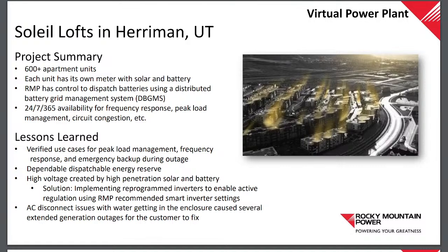So this last summer, Soleil contacted us and said, hey, we're getting some high voltage, and we said, well yeah, we have 600 batteries and things connected right there, you're going to have high voltage. So we did some testing, some measurements, found some three-phase transformers around, and had recorders set at their transformers serving the apartment complex. They had high voltage, but not outside their complex, so we had it narrowed down. We lowered the voltage at the substation and at the homes a little bit, but they were still getting high voltage. So we came up with a solution.